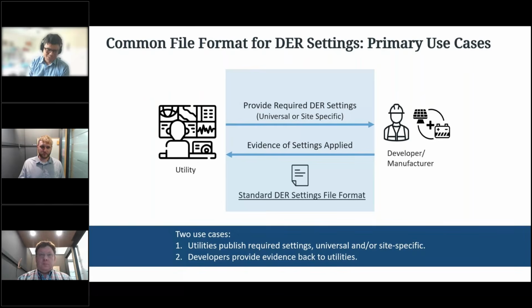The other way is also true. During the interconnection process, the utility at some point asks for evidence - that's the arrow going from developer to utility - where you as the installer need to send evidence saying you've programmed the DER correctly. A couple of years ago, one of our partner utilities called us and said they received about 300 photographs from installers, photographs of LCD screens claiming to be proof of how they'd programmed the DER, and they didn't know what to do with that.